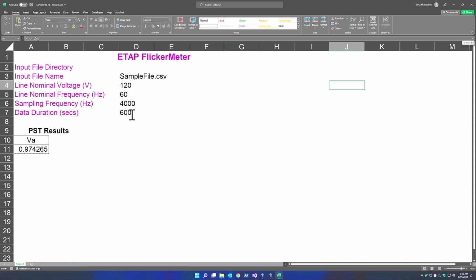And you can see this data file was only 600 seconds, so not long enough to compute the long-term index, but long enough to compute the short-term index. And we can see for the voltage magnitude for phase A, the short-term index is 0.97. And then of course this can be evaluated against the emission limits to determine whether we have good power quality within this network or not.